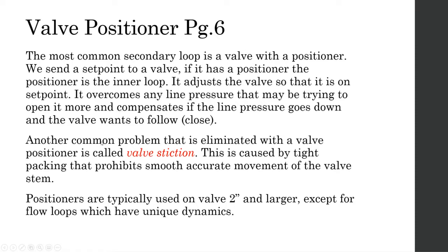Another common problem that's eliminated with the positioner is called valve stiction. We've mentioned valve stiction a couple of different times, and that's caused again by tight packing that prohibits smooth movement of the valve stem.